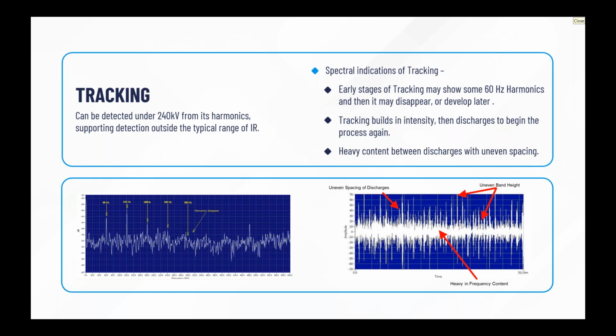Now, the next one that we look at is tracking. So typically, it can sound similar to corona, but it is much more aggressive. The most common way of describing it is going to be bacon and eggs in a pan, just lots of snaps and crackles. You still have that buzzing from corona, but it's much more aggressive. You do have snaps, cracks happening. Typically, what we see, especially as it becomes more and more severe, in that line frequency, it will eventually start to drop off. As in this left image, we have it continuing on, and then it starts to fade out.